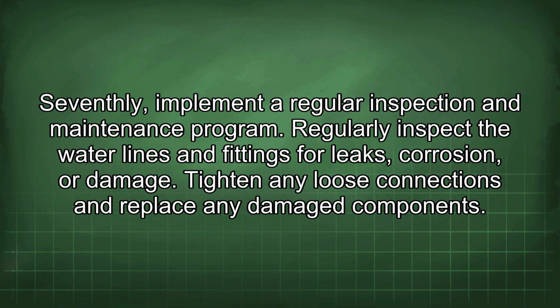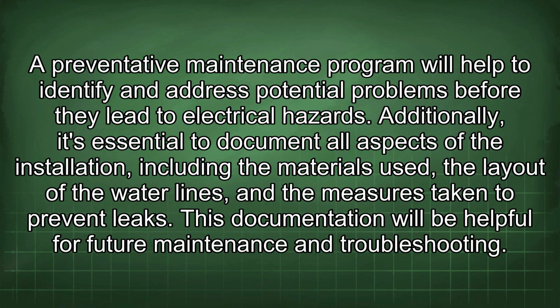Seventhly, implement a regular inspection and maintenance program. Regularly inspect the water lines and fittings for leaks, corrosion, or damage. Tighten any loose connections and replace any damaged components. A preventative maintenance program will help to identify and address potential problems before they lead to electrical hazards. Additionally, it's essential to document all aspects of the installation, including the materials used, the layout of the water lines, and the measures taken to prevent leaks. This documentation will be helpful for future maintenance and troubleshooting.